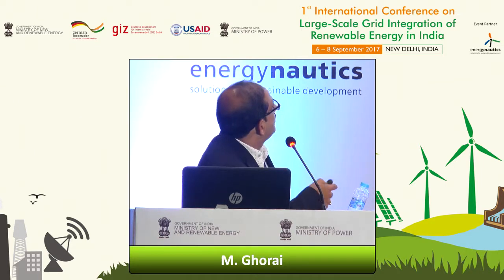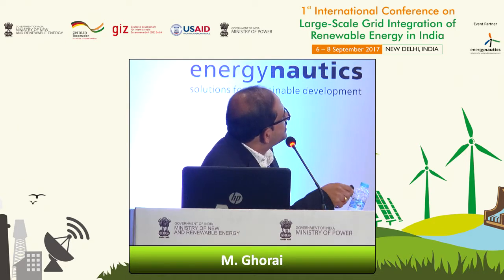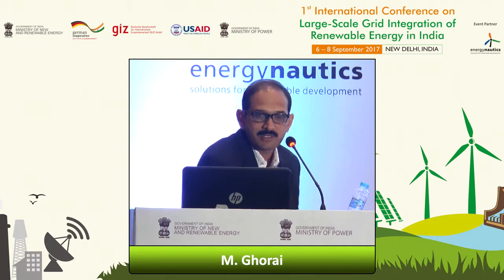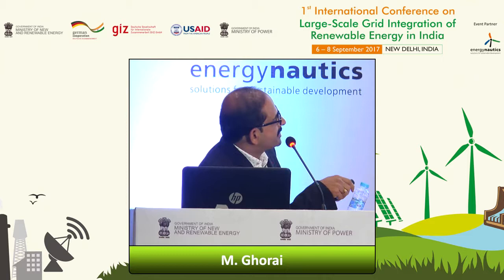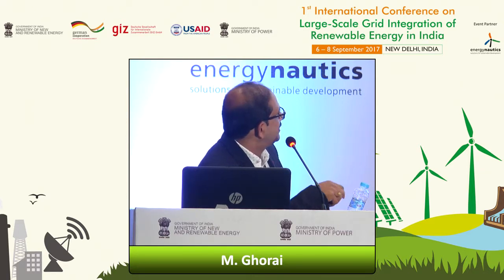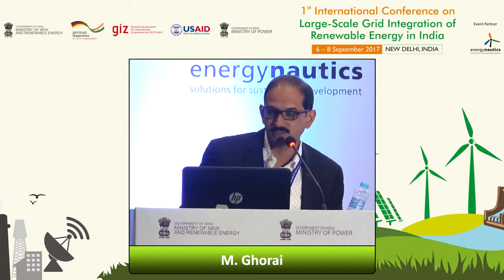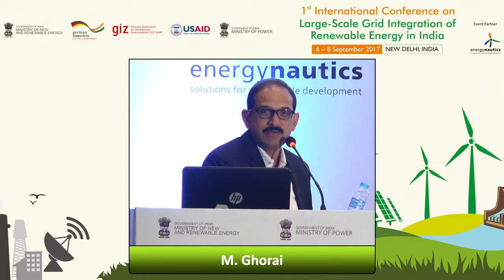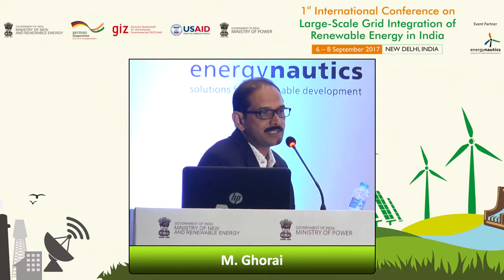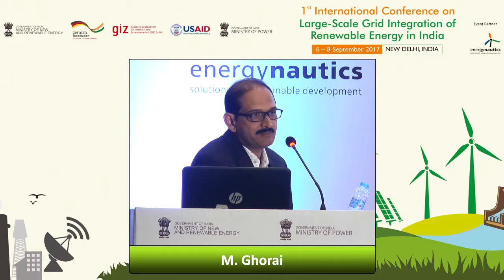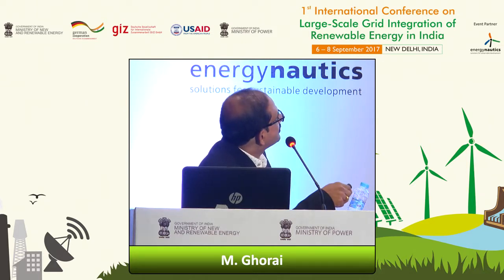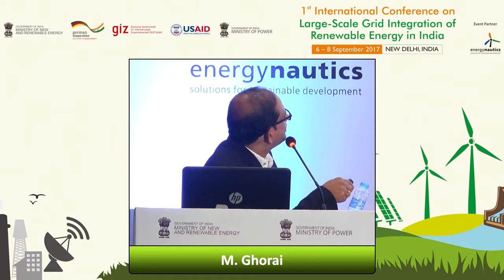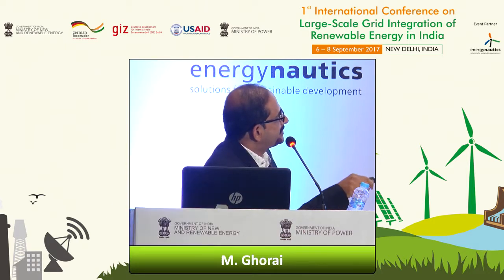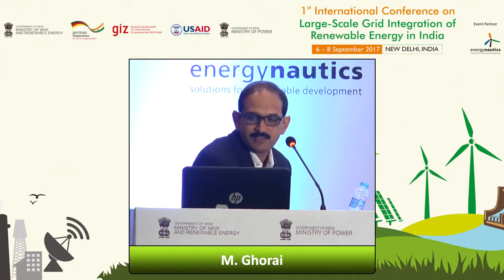So we did some simulations and showed the reactive power current which needs to be injected. This point lies here. Also, two events really happened a few months after commissioning of our wind farm, and we analyzed them using high-speed graphs. Through that analysis, it again met the grid code requirements.